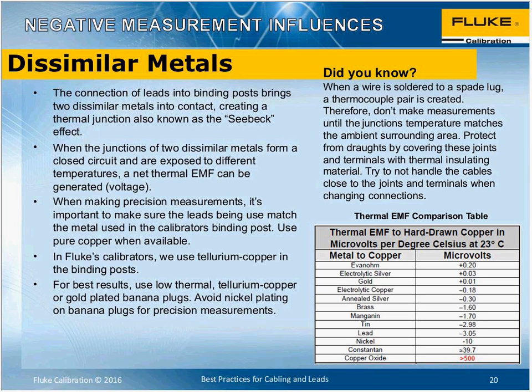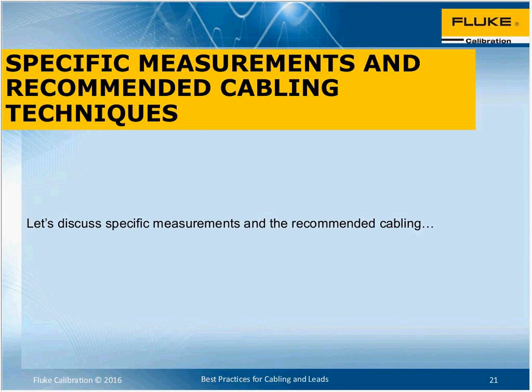Let's handle the end of the lead where the sensitive part is, hold the lead a bit further down, and be aware that, of course, even the joints are a problem, and the lead terminates at the end between the physical metal wire of the lead with the material of the jack or connector, and then the terminals. So keeping the terminals at the same temperature by putting insulation around them, minimizing drafts in the environment and so forth, are all good mitigation efforts that we should follow.